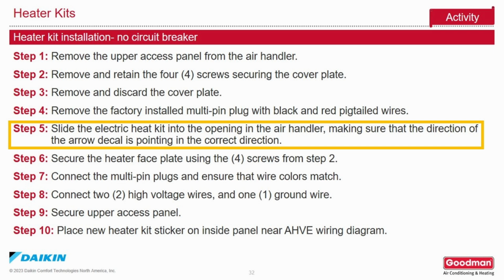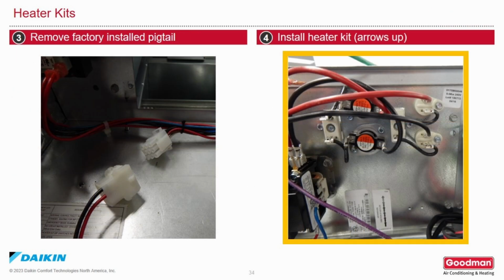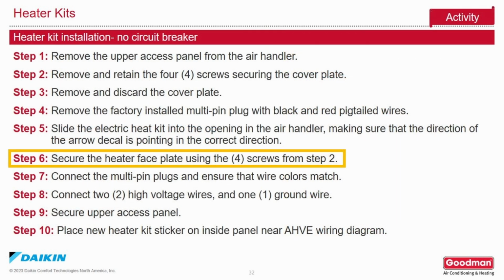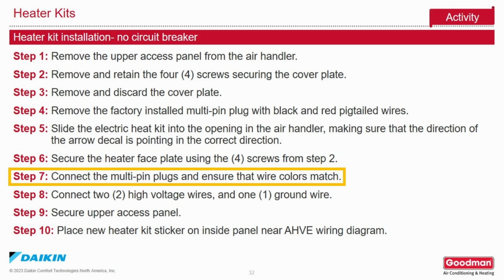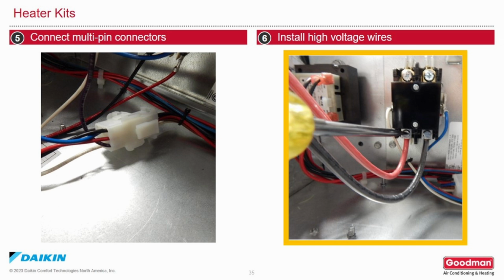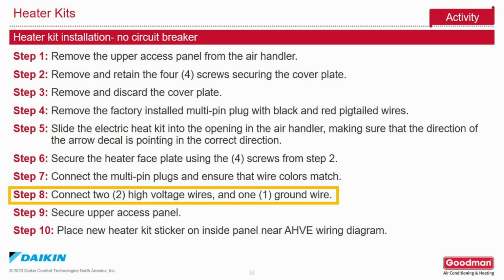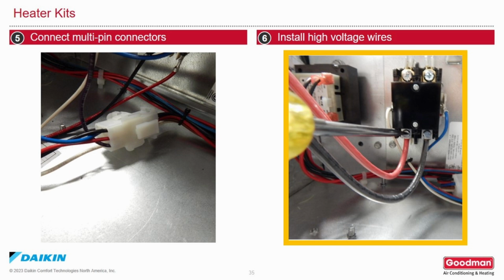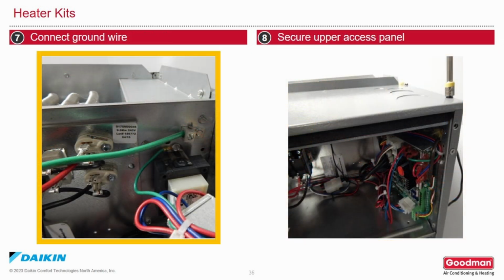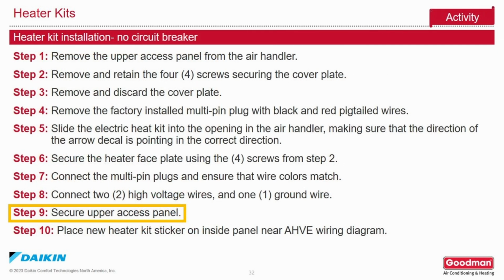Slide the electric heater kit into the opening of the air handler, making sure that the direction of the arrow decal is pointing in the correct direction. Secure the heater faceplate using the 4 screws from step 2. Connect the multi-pin plug and ensure that the wire colors match. Connect 2 high voltage wires and 1 ground wire. Secure the upper access panel.